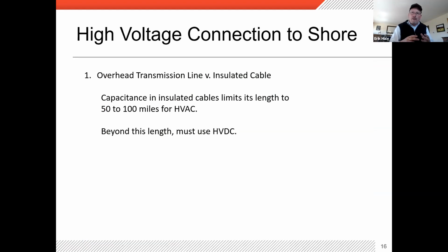There's a physical property of this cable called capacitance, and it's going to limit the length of the cable to roughly 50 miles. There are a few tricks you can play to get more distance out of that, but if you're going to use AC, you're going to be limited to this. This is one of the reasons high voltage DC is being considered for this purpose, and is a likely solution if we're going to go long distances with cables on the ocean floor.